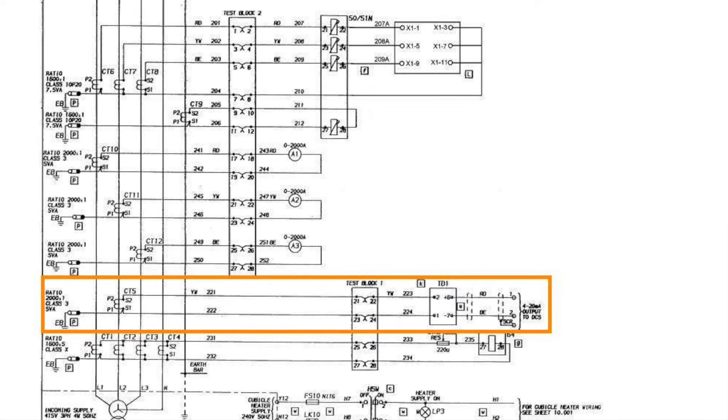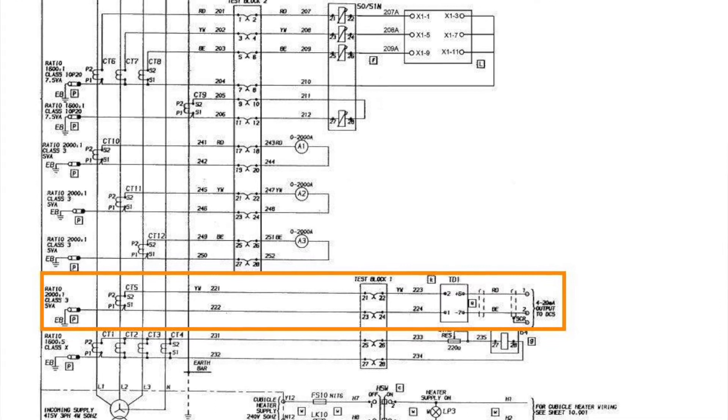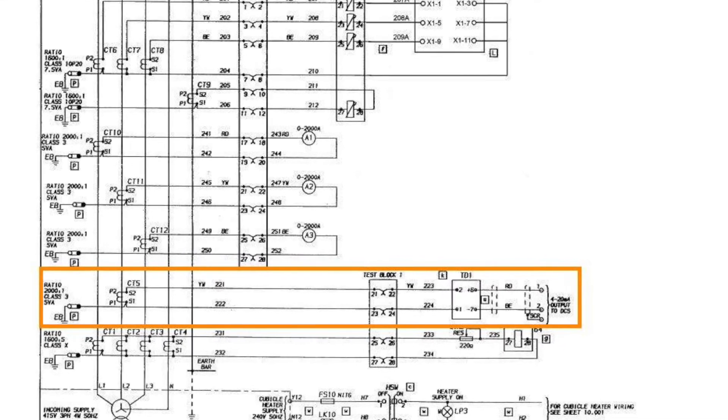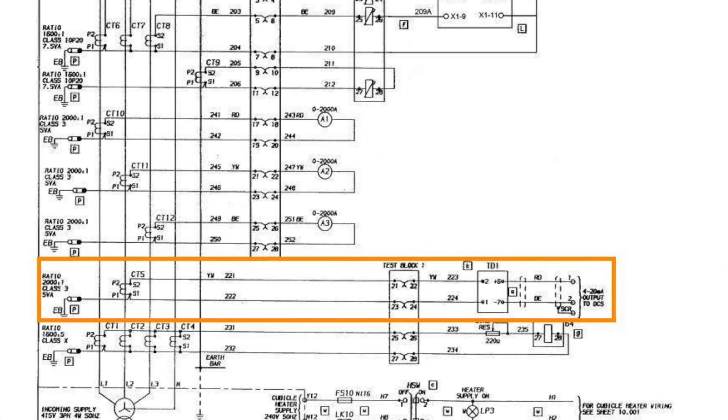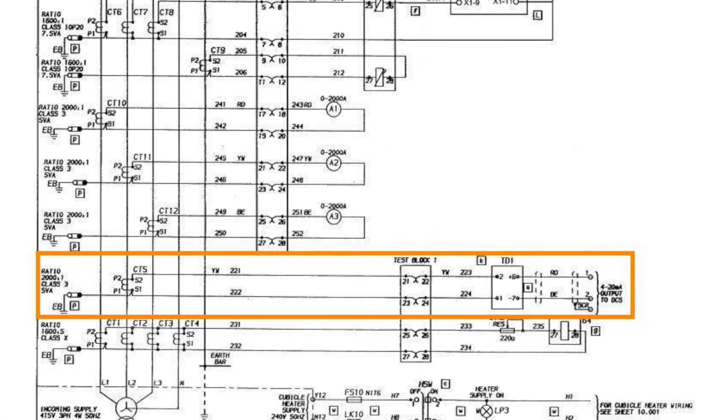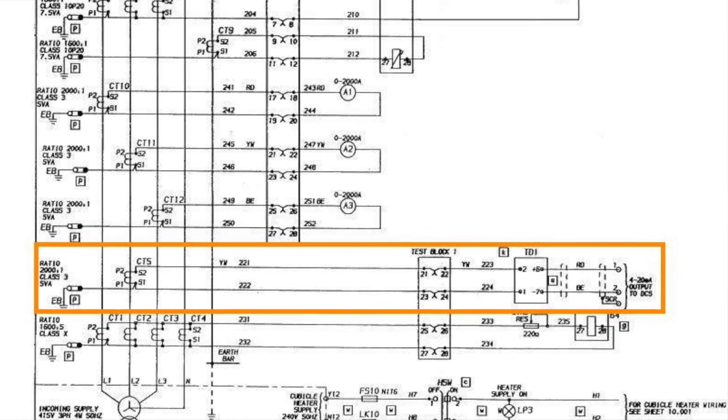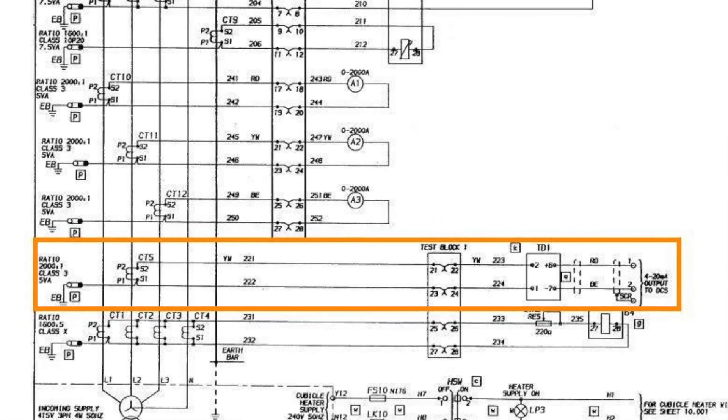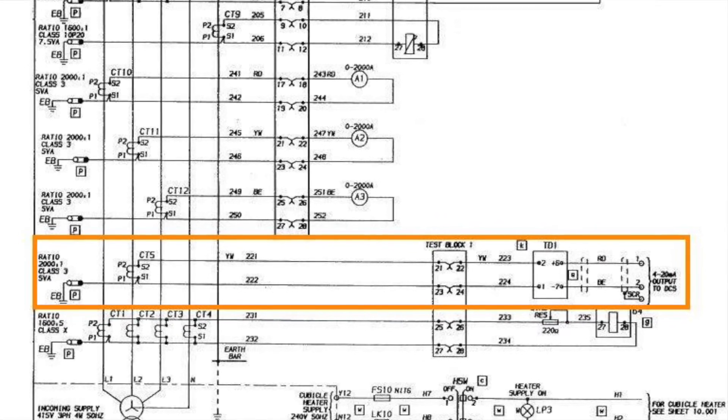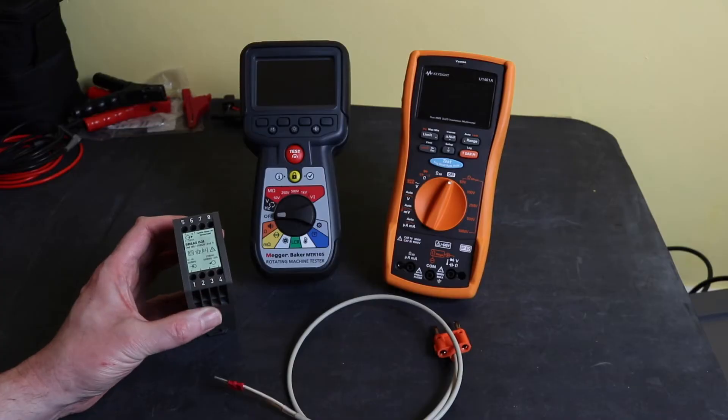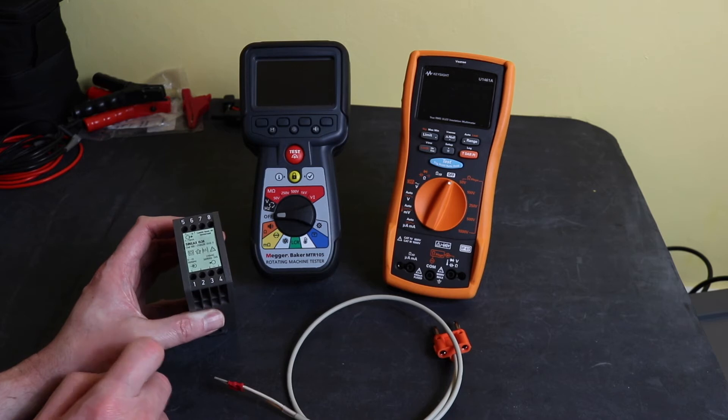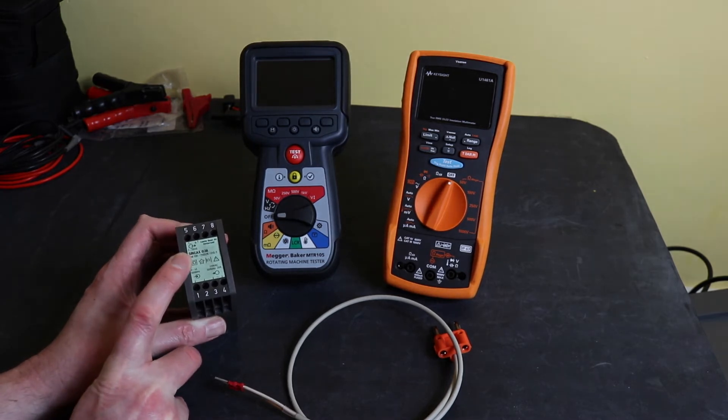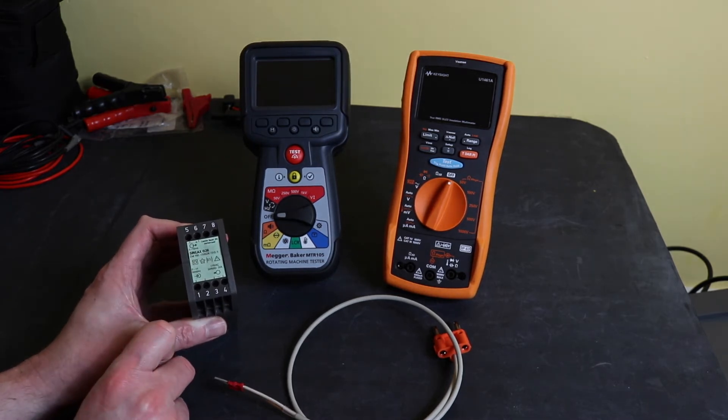You'll see on the far left hand side there is a single current transformer called CT5 that has a 2000 to 1 amp ratio that feeds through. It feeds via the test block straight into the current transducer such as this one here. That would be the 0 to 1 amps that would come in on terminals 1 and 2 here. And then on the output would go 4 to 20 milliamp out to the control system.